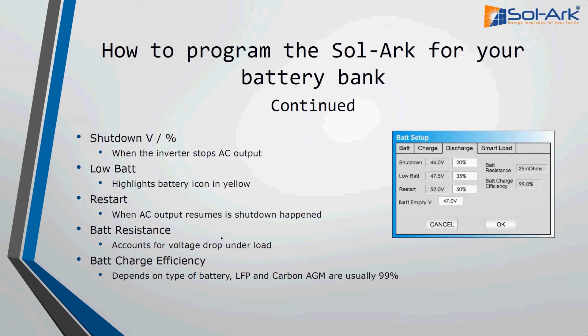One is to prevent damage to the inverter and the battery when you're off-grid. So if you're discharging your battery bank and you hit this voltage, we're going to turn the inverter off before the BMS turns itself off, because it's not really good to disconnect the battery from the inverter whenever it's under heavy load. So it saves both parties there.